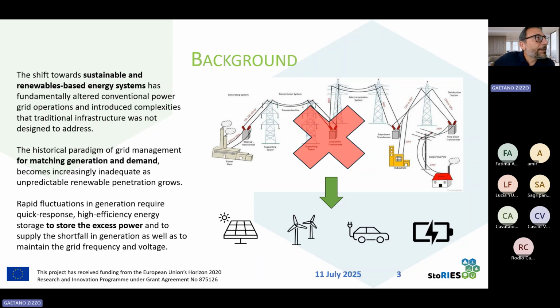As an example, the spreading of distributed generation, so the spreading of new generation units connected to the medium voltage and the low voltage grid, has caused a lot of problems, in particular in the primary cabin, at the node where we have HV and MV transformers, because in some areas we have reverse power flow. So we have an active power flow from the distribution to the transmission grid. This is a new situation that, for example, our protection devices were not ready to face.